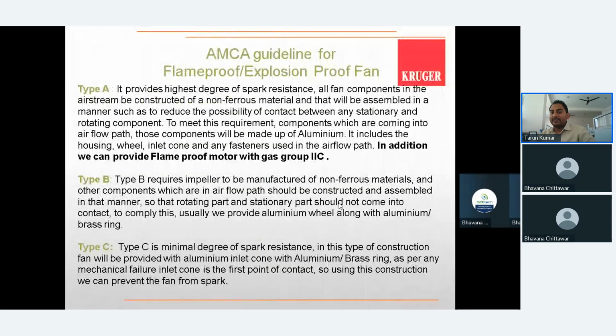AMCA has given a guideline. AMCA is the body which certifies the fan, probably everyone is aware. Suppose we claim a fan is designed for 50,000 CFM or 60,000 CFM. They take the fan into their lab, check and verify that it can deliver this much CFM and static pressure, and give the certificate to every fan manufacturer. It is mandatory. At the same time, ATEX is a third party body which certifies the fan so that it can be used for flame proof applications.